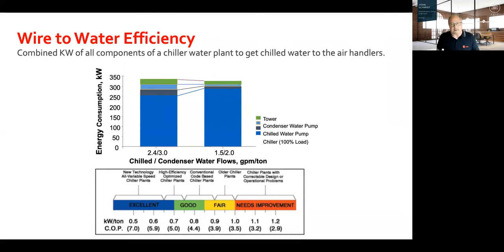So if we're not hitting that 0.7 kW per ton for the entire plant, that's all the pumps, tower fans, chiller itself, we know there's room for improvement. So we're going to look elsewhere, whether it's controls or design or whatever the case may be. So you might be metering your plant, and if you are, those are good benchmarks to gauge your efficiency with. Next slide, please.